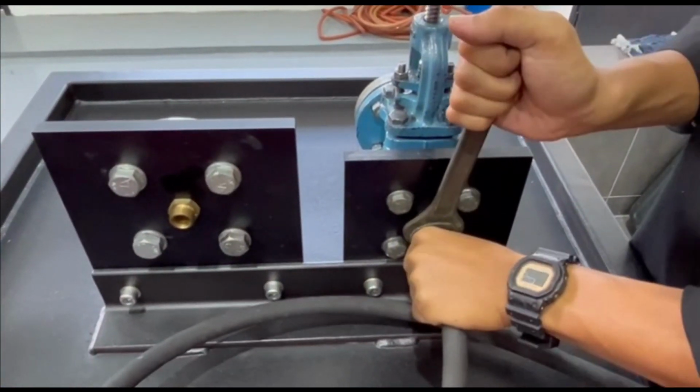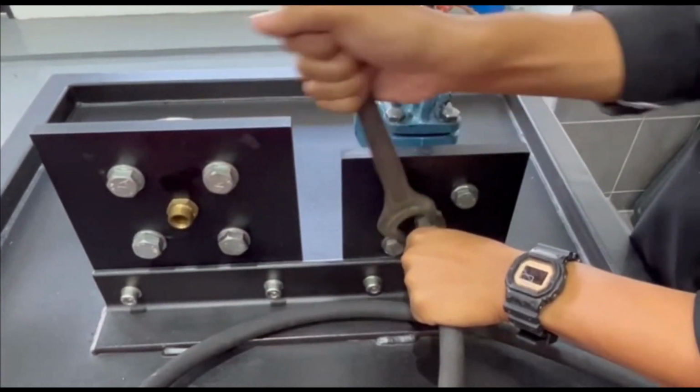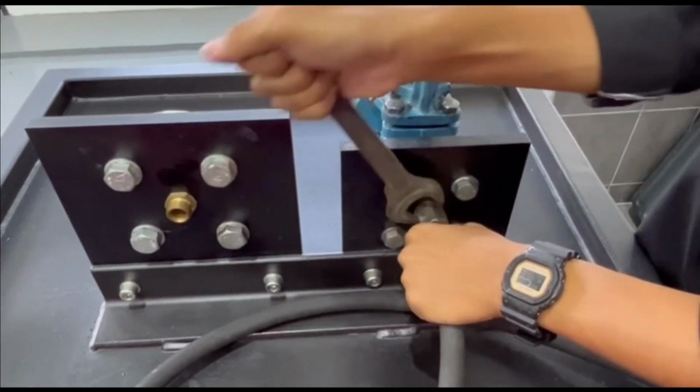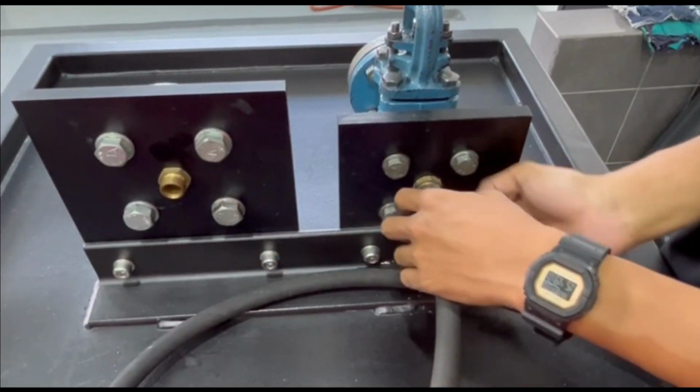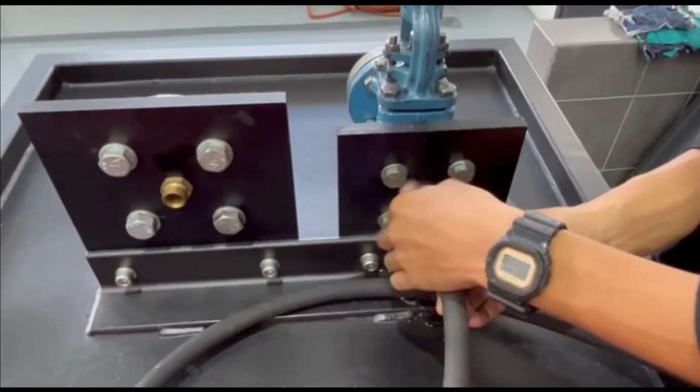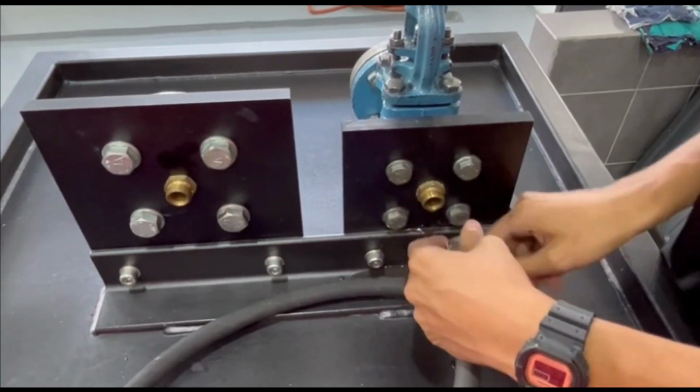Furthermore, the leakage at the hose location is primarily caused by damaged or worn-out seals that do not perform the required role of preventing the water from leaking. This sort of issue can be resolved by changing the seals to ones that correspond to the shut-off valve requirements.